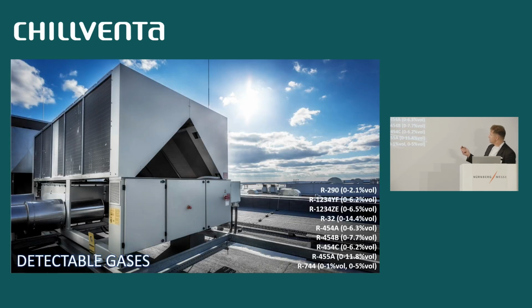Our gas list, mentioned before: all major A2L gases are there, as well as R290 or propane, as well as CO2 in different ranges. All the major A2L gases are provided in their classic LFL, so a lower flammable limit range. In percentage of volume here is expressed, but each of these ranges is actually the LFL.